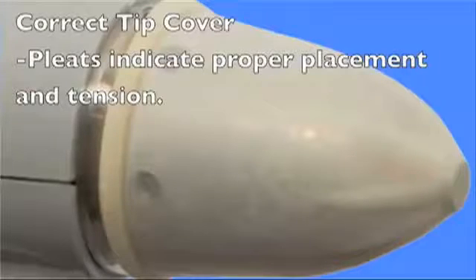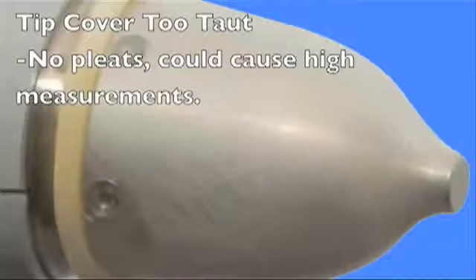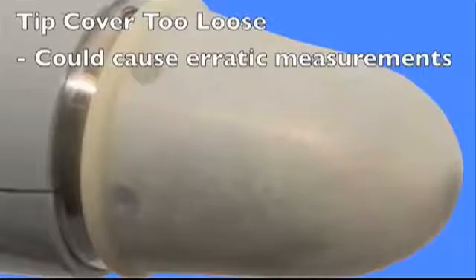Pleats indicate proper tension while allowing the transducer pin to move freely. Tip covers that are too tight can introduce false resistance to the transducer pin, and IOP measurements can read higher. Tip covers that are too loose can fold over or crease and possibly create erratic measurements.